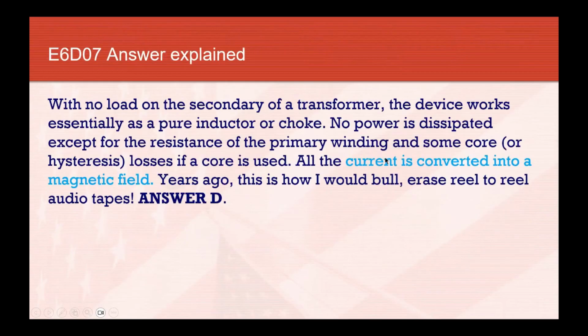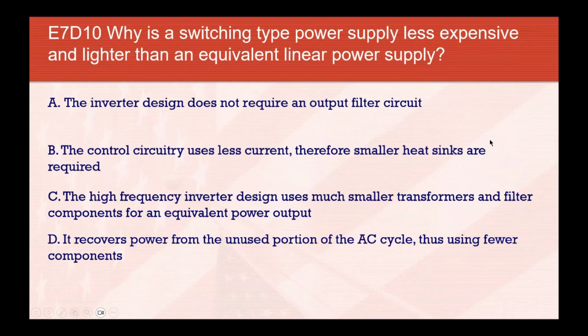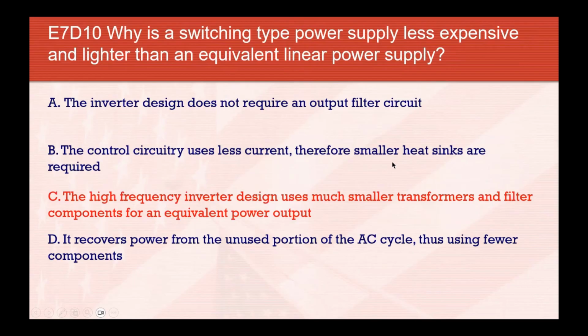So it's magnetizing current. Why is the switching type power supply less expensive and lighter than the equivalent linear power supply with a great big old heavy transformer and lots of capacitors? Because it can use high frequency components that are much smaller, because the filtering is much easier when we're using much higher frequencies. So the high frequency inverter design lets us use smaller transformers and filter capacitors.